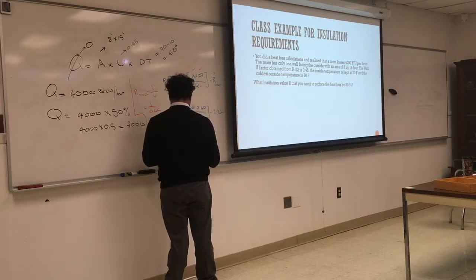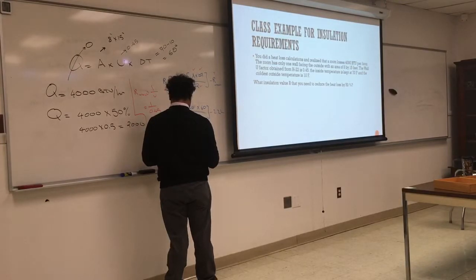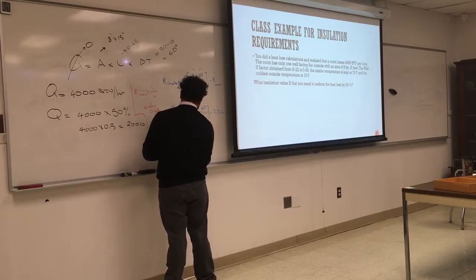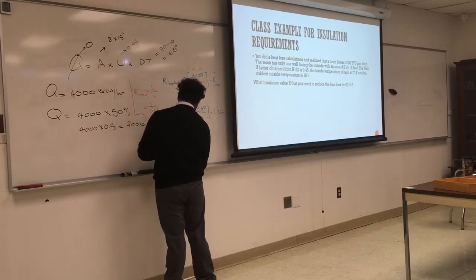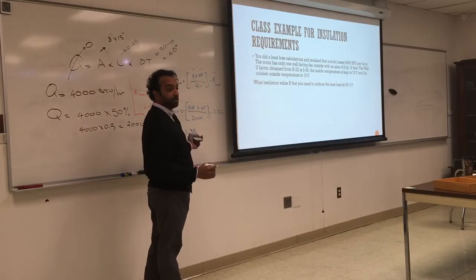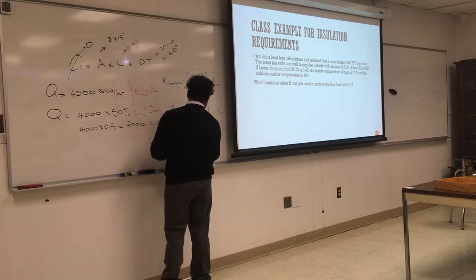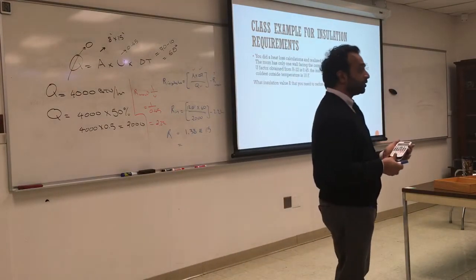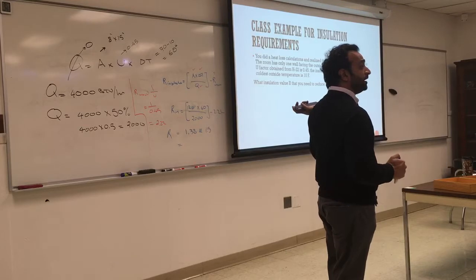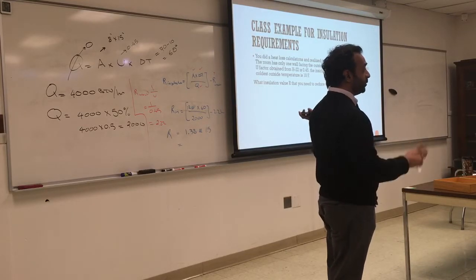One point three eight. Why would it be 120? So it's 1.38. It's the R value. So probably you're not going to find 1.38, you're going to go to 1.5. So this means an approximation of 1.5. That's doable, that's cheap. You'll put that in and you will reduce the heat loss by 50%, that's a lot. So that's how much insulation R value you would add.